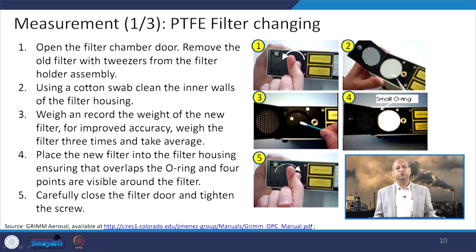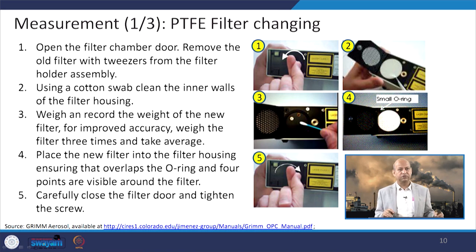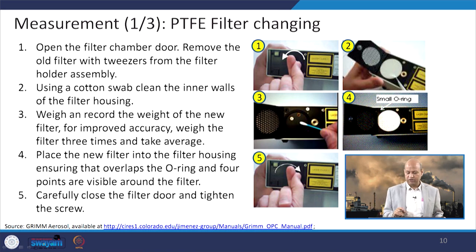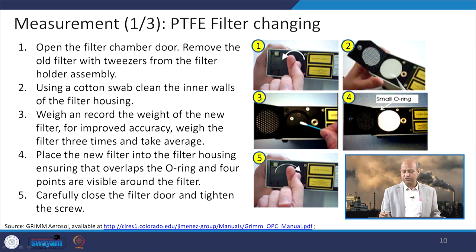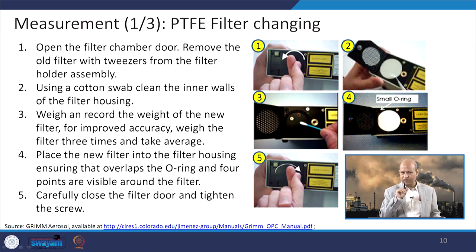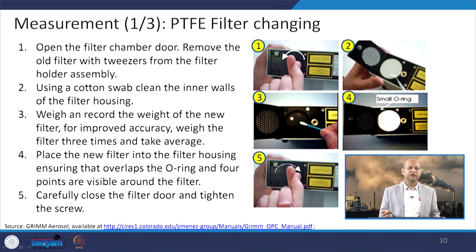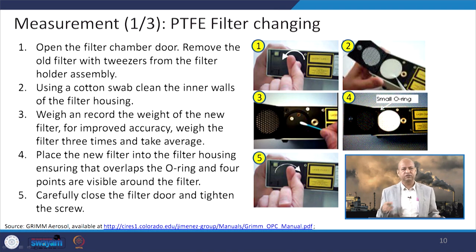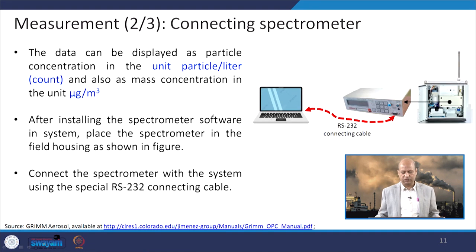When doing monitoring, we should be particularly careful about how to insert the filter paper. Remove the old one using tweezers, clean the housing properly, then put in the new filter paper. It has to be weighed three times because it is small, and the average weight is taken after weighing it three times before monitoring begins.